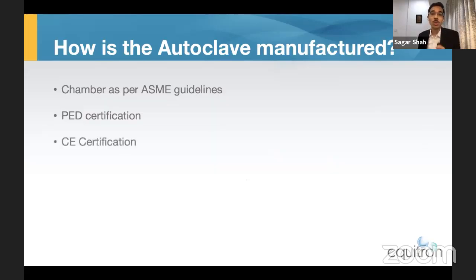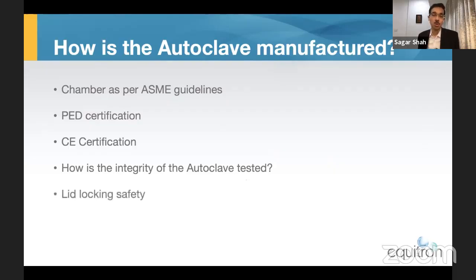You would also want to ensure that the autoclave has CE certification. And finally, do inquire how the integrity of the autoclave chamber is tested. Hydro testing the autoclave is a gold standard in verifying the integrity of most pressure vessels. So that's something that you would want to check with the autoclave manufacturer. And finally, you would want to check on the door locking safety of the autoclave.